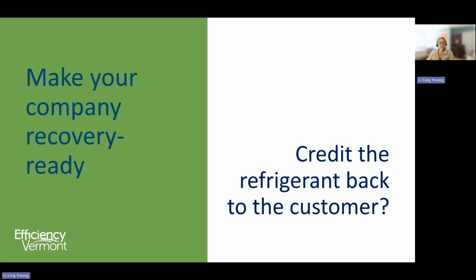And then finally, something to think about. In this age of refrigerant transitions, recovered refrigerants have a market value if they're clean enough. And you may want to credit back the payment that you get on the recovered refrigerant to the customer. It just makes the whole transaction more transparent and emphasizes the importance of recovering refrigerants.